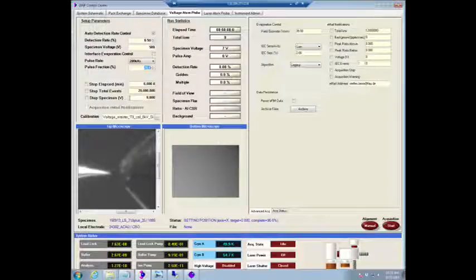You will see when the concentration starts changing in your measurement results, okay? 20% for most steels and superalloys is actually a pretty good starting point. But this is very, very important. So pulse fraction and temperature are probably the two most important settings that you have. The rest is just you can tell the atom probe to stop after a certain time, after a certain number of events, or at a certain specimen voltage.